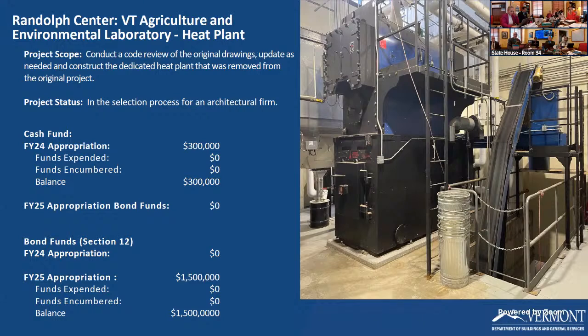The other issue is they do not use their heat plant during the summer - they, like here in Montpelier and Waterbury, shut down. So now they're having to use a large boiler to maintain the steam coming to the lab in short cycles, meaning it comes on, tops off that steam pressure a little bit, then shuts off and waits for it to drop, then restarts again. It's constantly doing that - there's just not a heavy enough load for the oil gun to come on and stay on. So that's one of the issues.